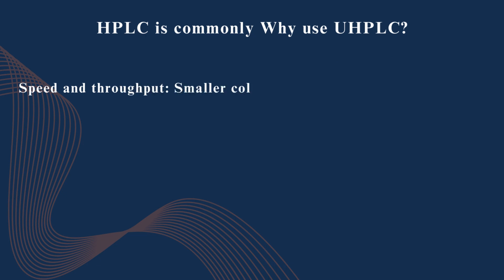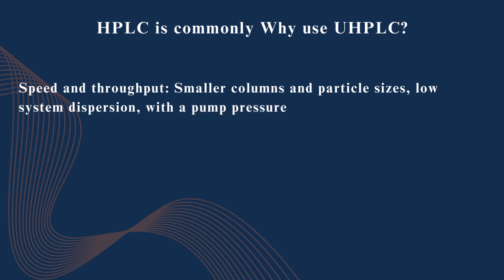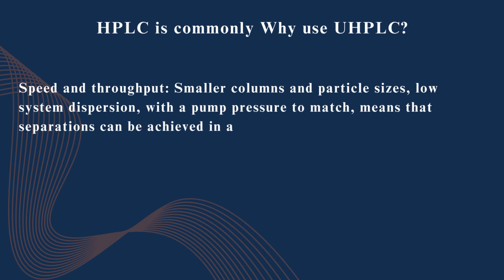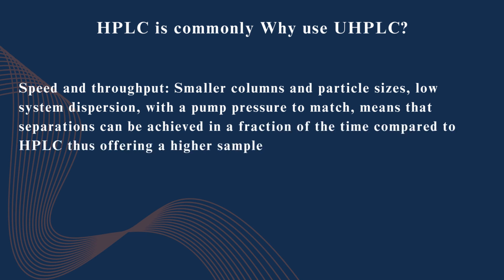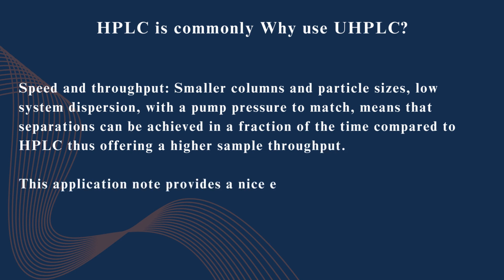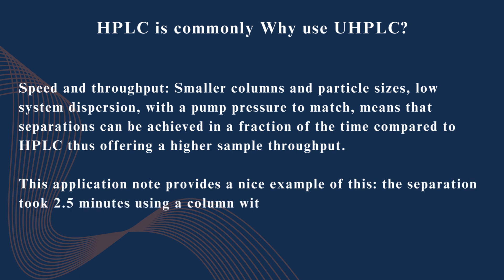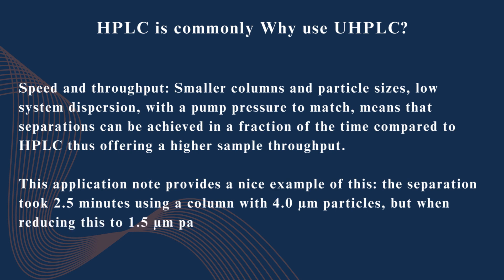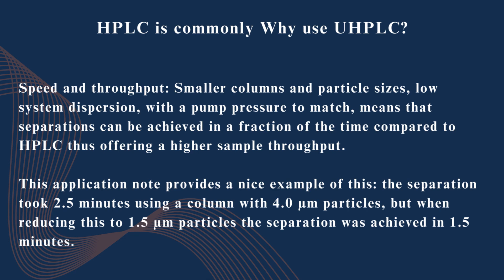Speed and throughput. Smaller columns and particle sizes, low system dispersion, with a pump pressure to match, means that separations can be achieved in a fraction of the time compared to HPLC, thus offering a higher sample throughput. This application note provides a nice example: the separation took 2.5 minutes using a column with 4.0 micron particles, but when reducing this to 1.5 micron particles, the separation was achieved in 1.5 minutes.